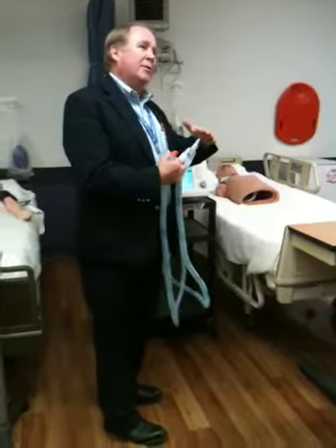You notice how the volume went up, or that blast of air comes out? That's because we have what's called PEEP. And it's saying, I'm trying to maintain PEEP, but there's nothing there. You've got a leak. But it will compensate for leaks.